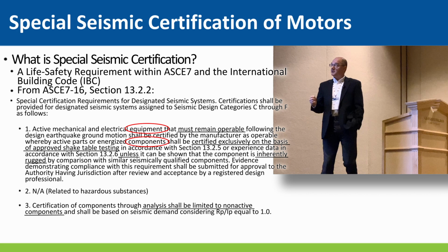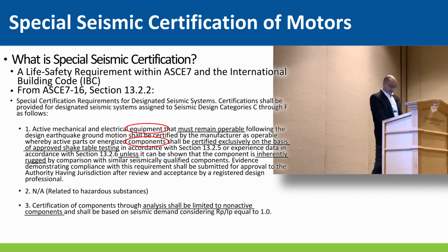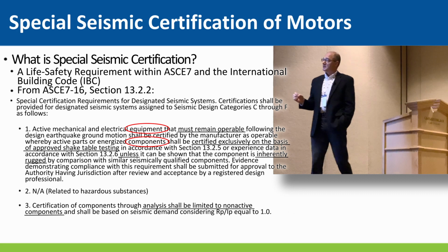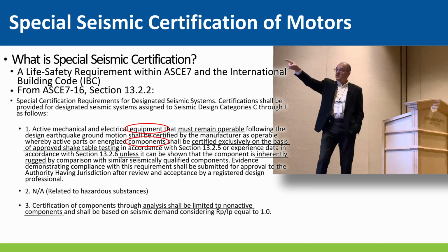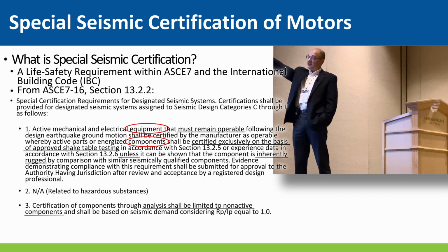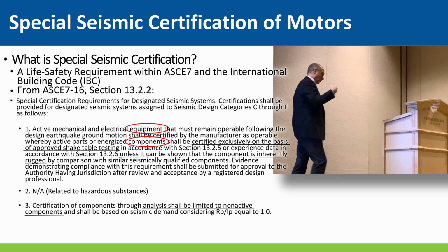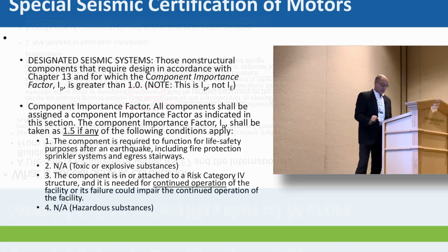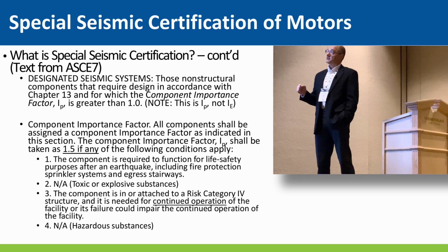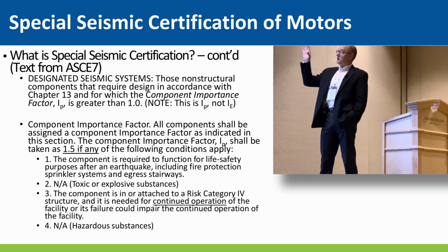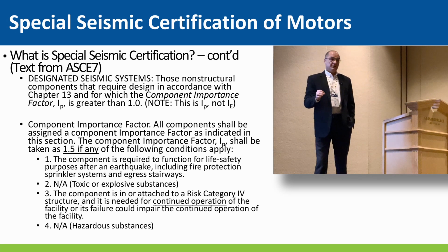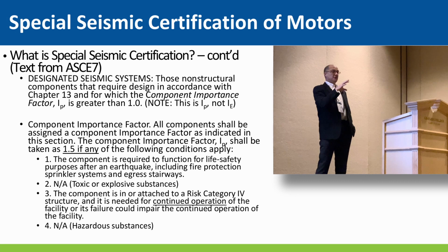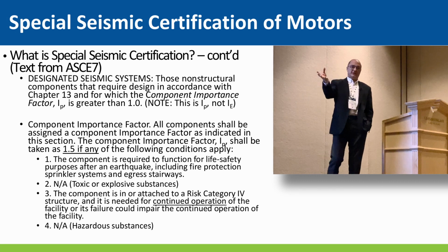Still going on, and so now I'm going to go back here. All right. So the opening bullet underneath section 13.2, special certification requirements for designated seismic systems. I want to go over what that means to you. Well, designated seismic systems are those non-structural components that require design in accordance with chapter 13, where the Ip is greater than 1.0. And the Ip is the importance factor of the part, which in this case is the equipment.